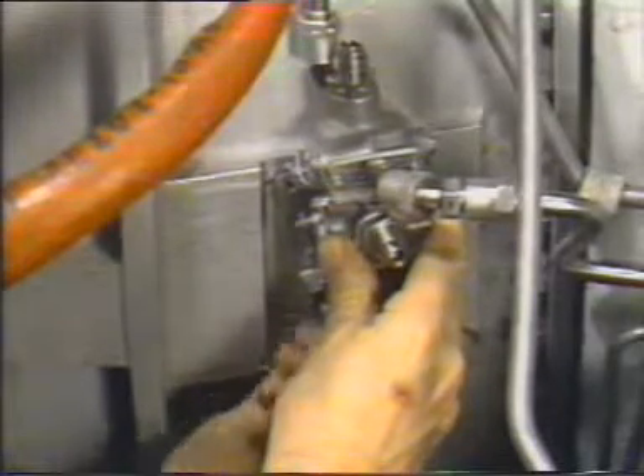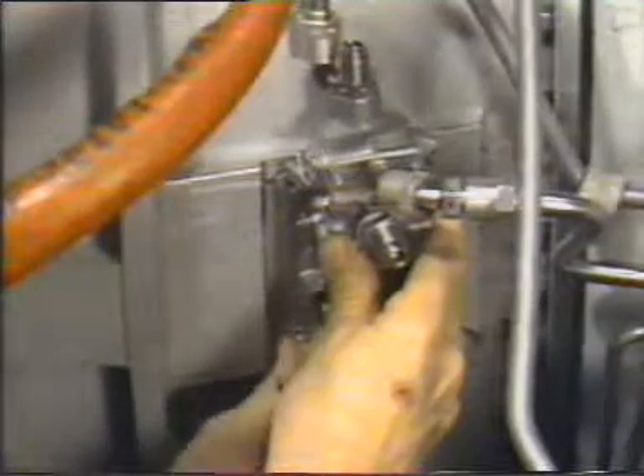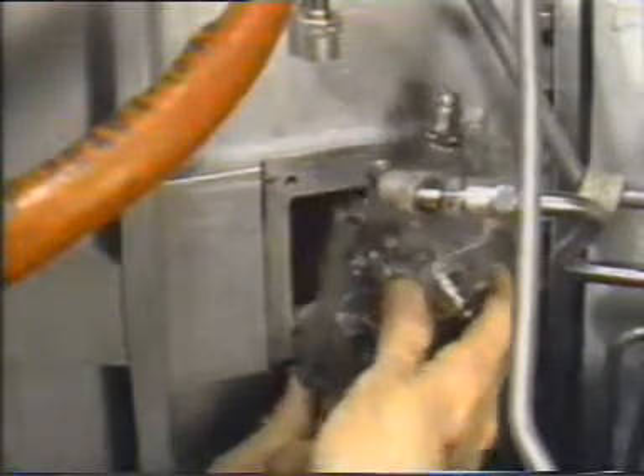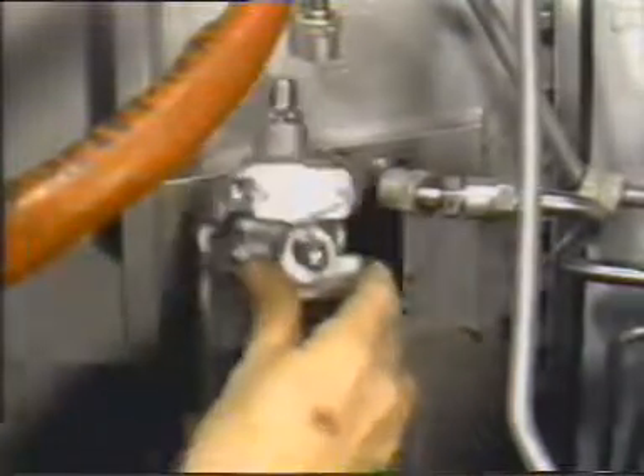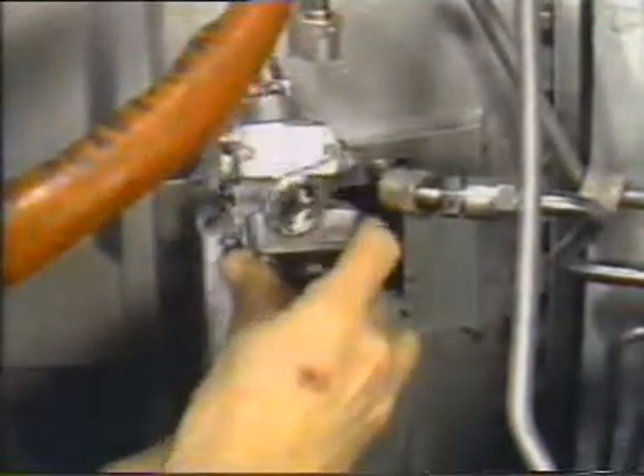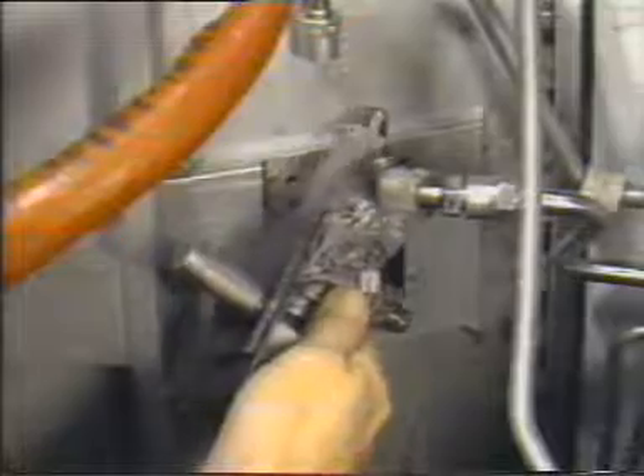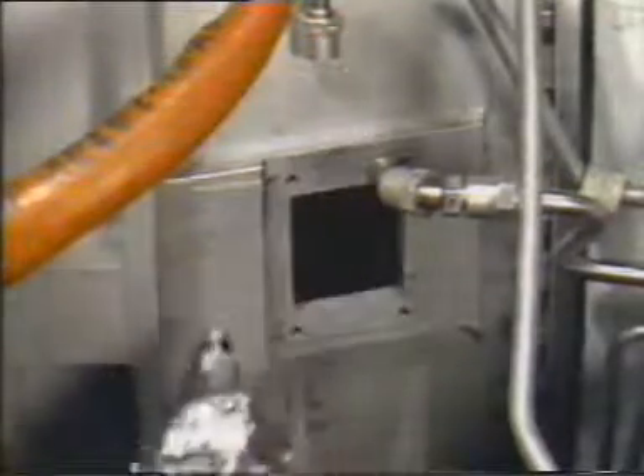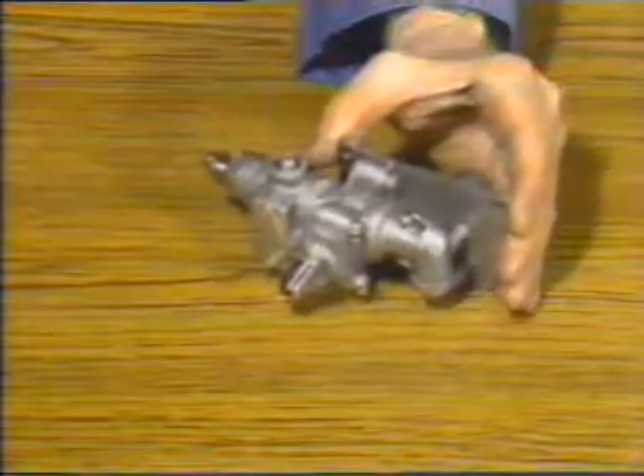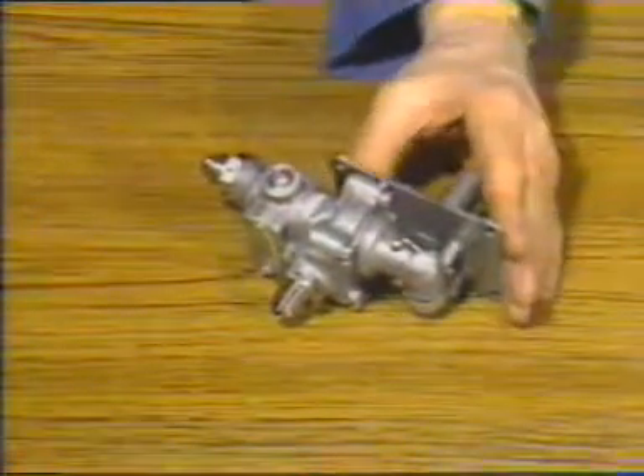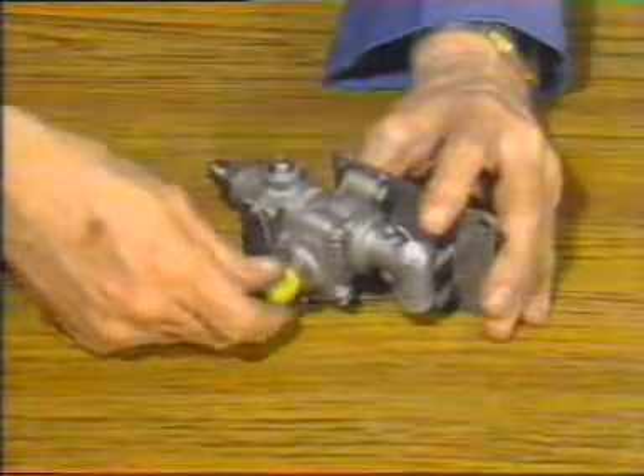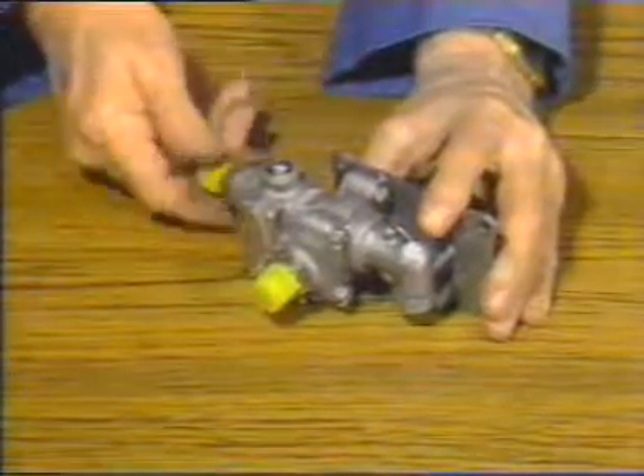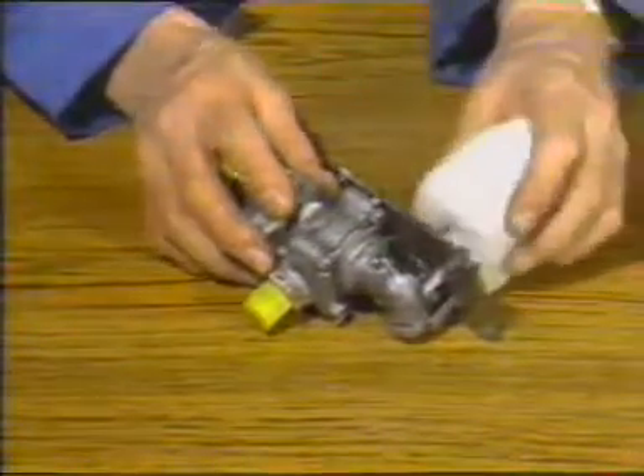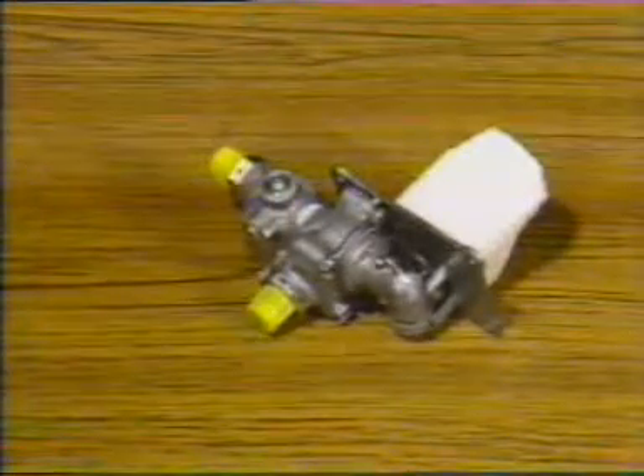Remove the CIT sensor from the gas turbine, exercising care to prevent damage to the helium-filled sensor protruding into the frame. Remove the gasket from between the sensor and the frame and discard it. Cap the CIT sensor fittings with plastic caps and install a protective cover over the sensor probe. The removal of the CIT sensor is complete.